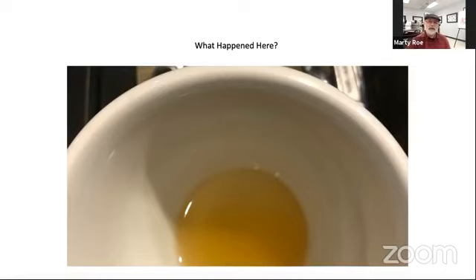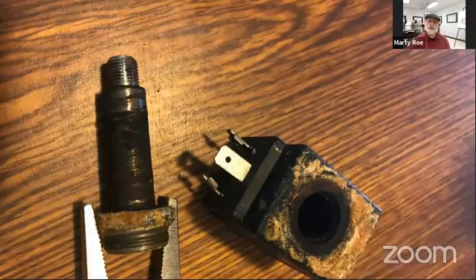The other recommendation: anytime you're on the schedule for changing your filters, we highly recommend totally draining that steam boiler and letting it refill with fresh water. That gives you another layer of defense in case you're not using enough hot water out of the spigot to maintain a clean boiler. So those two things are big: flush your steam boiler whenever you're changing filters, and use that hot water spigot as much as you possibly can.